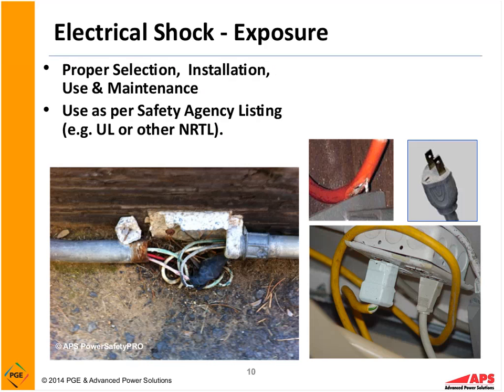So I've just given you a couple examples of exposure here. On the next slide, you can see the damaged equipment. This is at a resort in Eastern Oregon where the raceway coming up here, the metal raceway, is broken. The whole junction box there is broken. So the ground path is totally disrupted. There is no equipment grounding going on there. So if someone comes up and there is a fault, one of the energized conductors makes contact with that conduit, there is no fault return path back. That whole system would stay energized.